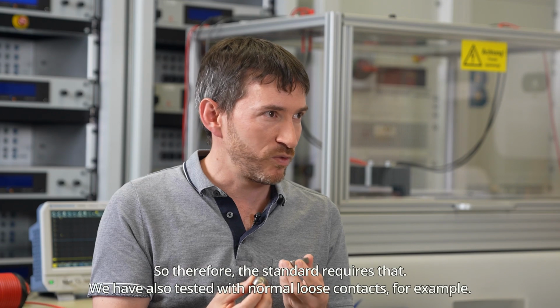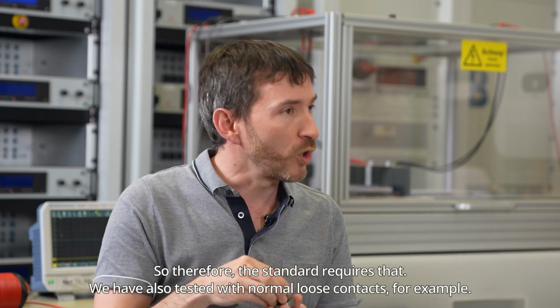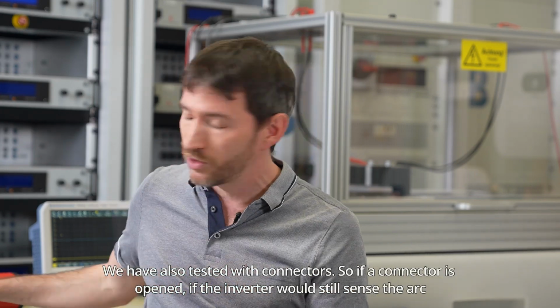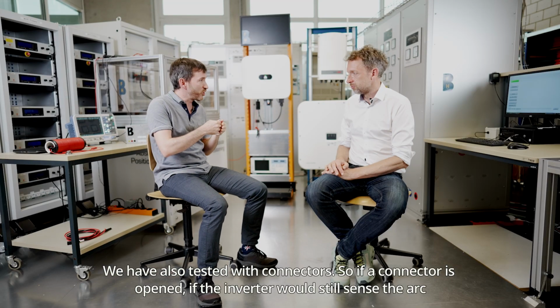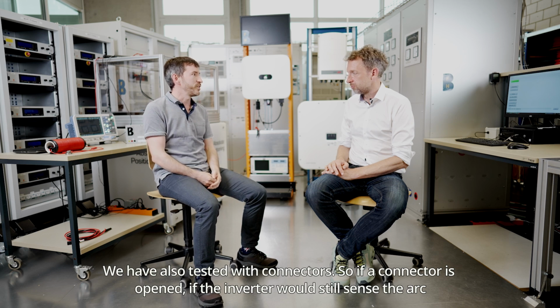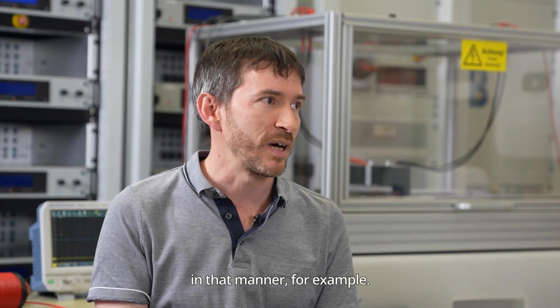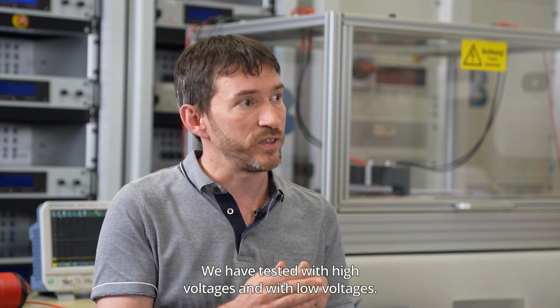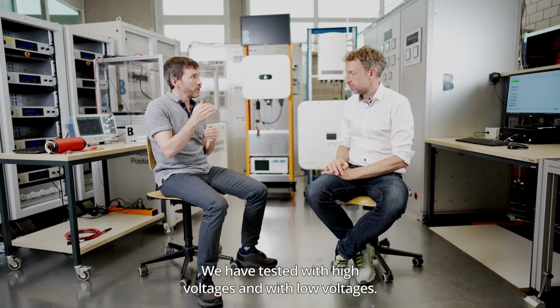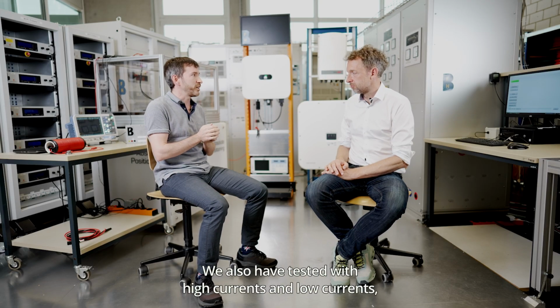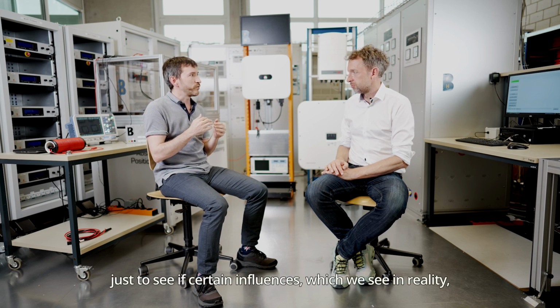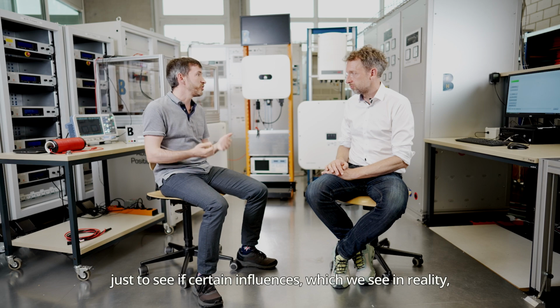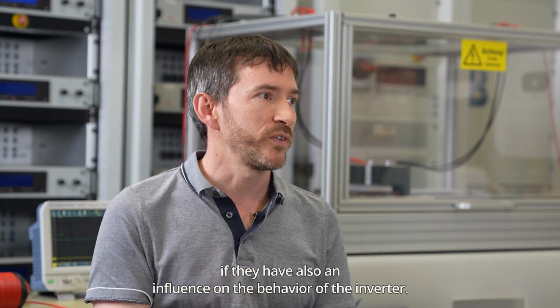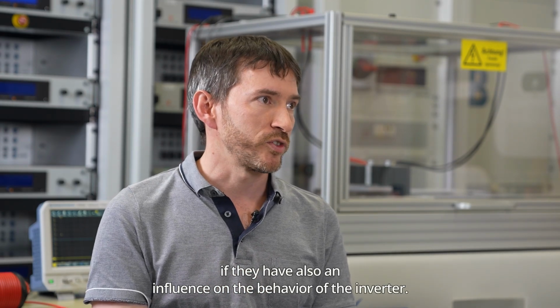We have also tested with normal loose contacts, for example. We have also tested with connectors, to see if a connector is opened, whether the inverter would still sense the arc in that manner. We have tested with high voltages and with low voltages. We also have tested with high currents and low currents, just to see if certain influences which we see in reality also have an influence on the behavior of the inverter.